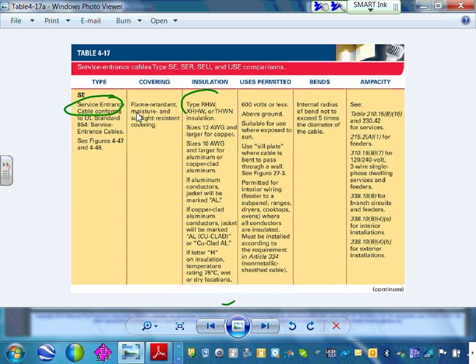Now, look at the insulation it comes with - it's flame retardant, moisture resistant, up to 600 volts. The internal bending radius is not to exceed - remember that 5 times the radius rule? For ampacity, you have to look at table 310.15(B)(16).